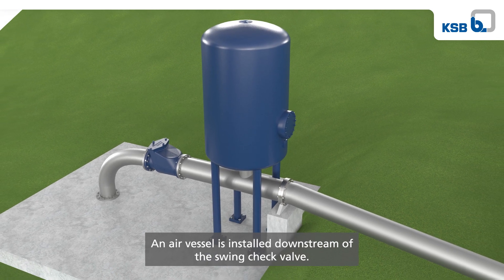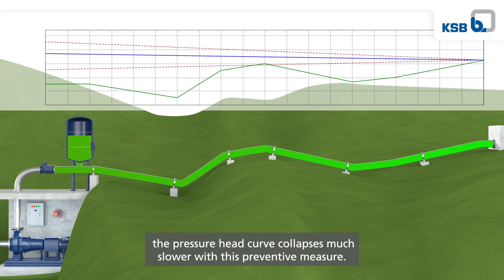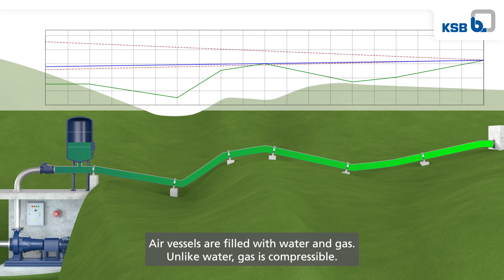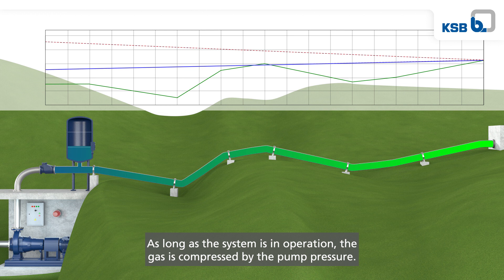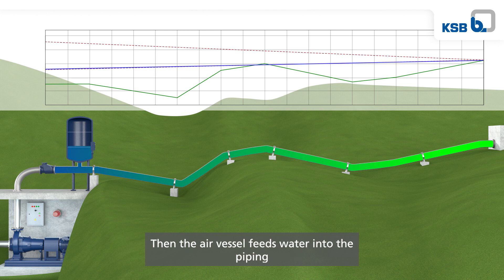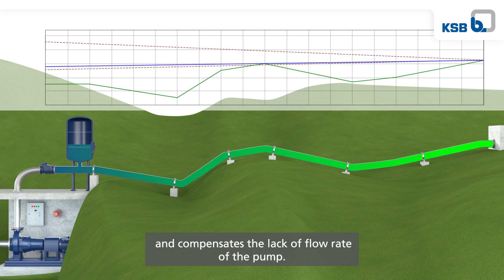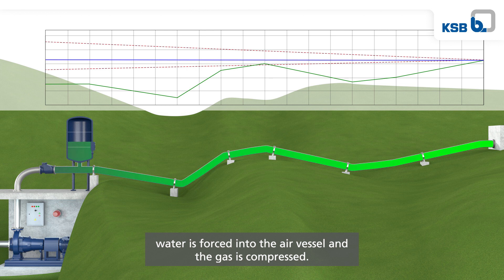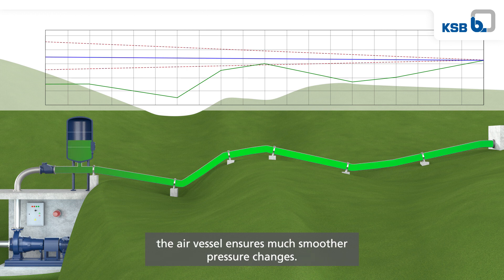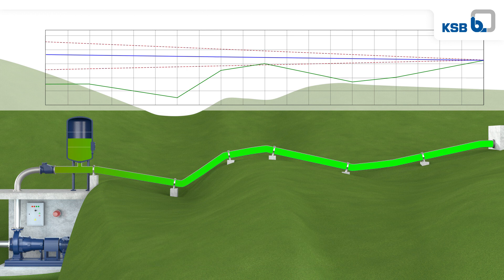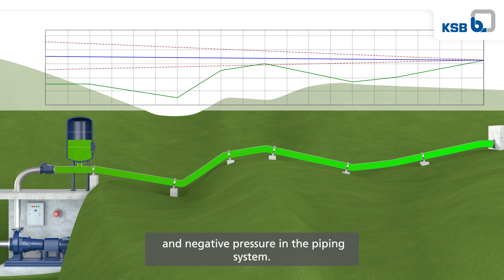An air vessel is installed downstream of the swing check valve. In the event of a pump failure, the pressure head curve collapses much slower with this preventive measure. Air vessels are filled with water and gas; unlike water, gas is compressible. As long as the system is in operation, the gas is compressed by the pump pressure. If the pump fails, the pressure drops and the gas can expand, allowing the air vessel to feed water into the piping and compensate the lack of flow rate of the pump. When a positive pressure wave approaches the air vessel, water is forced into the air vessel and the gas is compressed, reducing the positive pressure. With its compensating effect, the air vessel ensures much smoother pressure changes. In contrast to air valves, this is a closed system — no dirt can be drawn into the piping at negative pressure. Air vessels can significantly reduce both positive pressure peaks and negative pressure in the piping system.